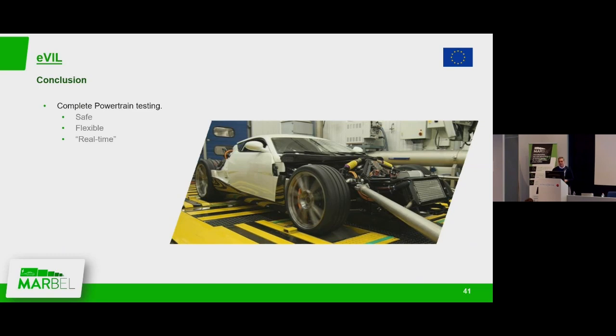Real time because we have only a small delay. We have checked the communication speed: it is about 3 or 4 milliseconds delay, but that is not a problem because our battery cycler has a refresh rate of 10 hertz, so the communication is faster than what the battery cycler is capable of reacting to.